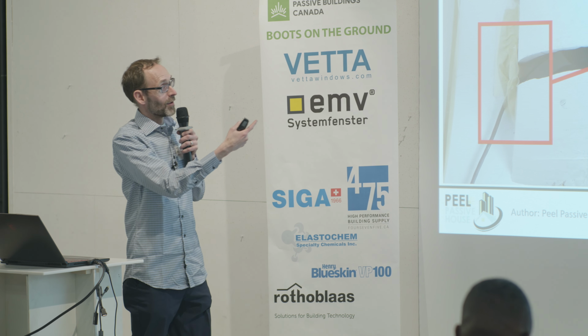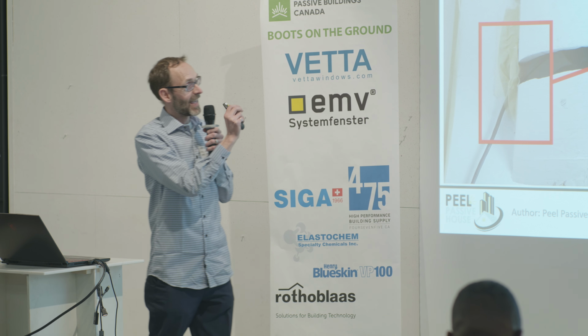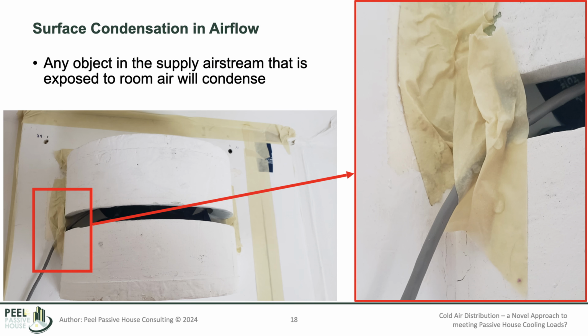Other things that were causing condensation - basically any item that's in the airflow that's also exposed to the room air will get condensation. You can see I've got sensor wire there going up, that gets condensation, it's dripping down. Tape, a thin layer of tape, that's enough to cause condensation - it was a magnet for condensation.